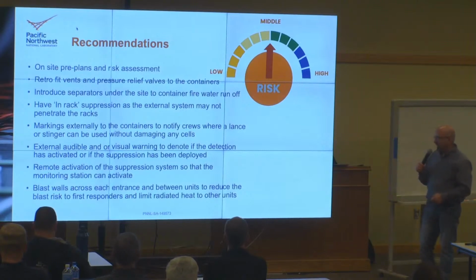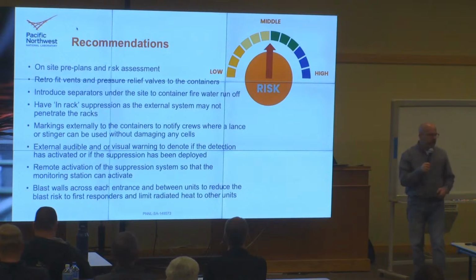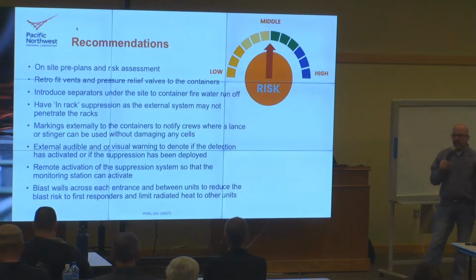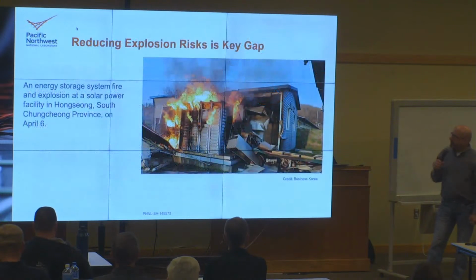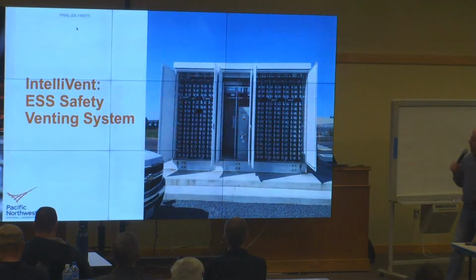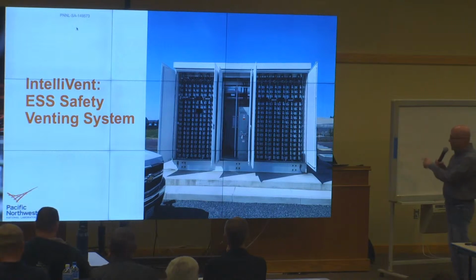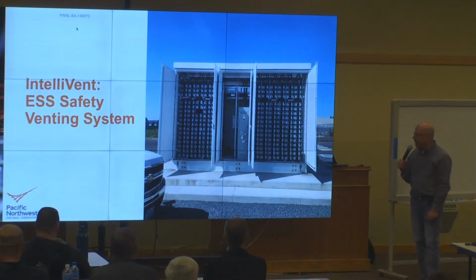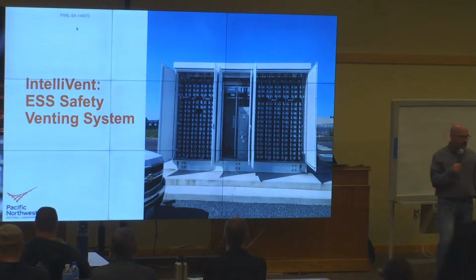Blast walls across each entrance and between units to reduce the fire blast risk. Again, deflagration prevention systems missing. Okay, so here's one in Korea. You saw that picture. So let me show you what we at PNNL thought might be an option for system designs. As an example, this is a 1.4 megawatt hour battery at a utility over in Arlington, Washington, Snowpud.